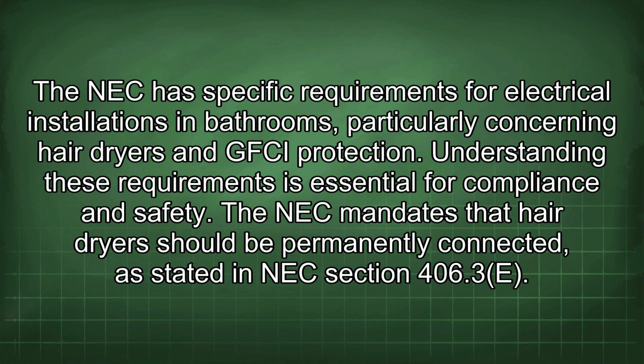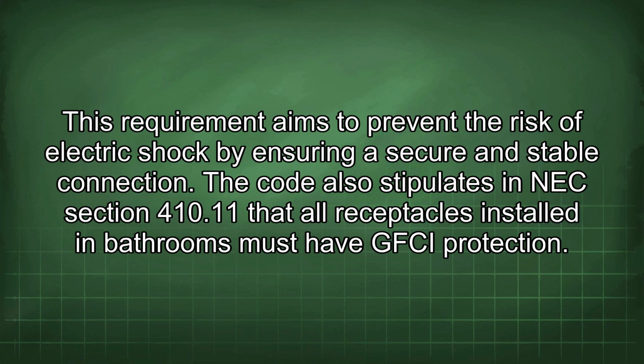The NEC has specific requirements for electrical installations in bathrooms, particularly concerning hairdryers and GFCI protection. Understanding these requirements is essential for compliance and safety. The NEC mandates that hairdryers should be permanently connected, as stated in NEC Section 406.3e. This requirement aims to prevent the risk of electric shock by ensuring a secure and stable connection. The code also stipulates in NEC Section 410.11 that all receptacles installed in bathrooms must have GFCI protection.